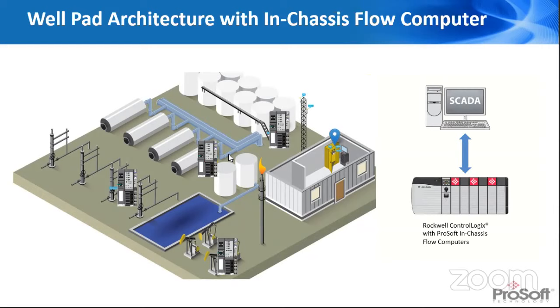So you can place I/O blocks such as Point I/O out at the wellhead, out at the separators, at the tank batteries themselves. And it helps reduce cabling. You're not having to home run all that wiring back to the control system. And it gives a very flexible architecture, so that as the well pad grows and additional I/O is needed, they can drop in an additional I/O panel with distributed I/O there.